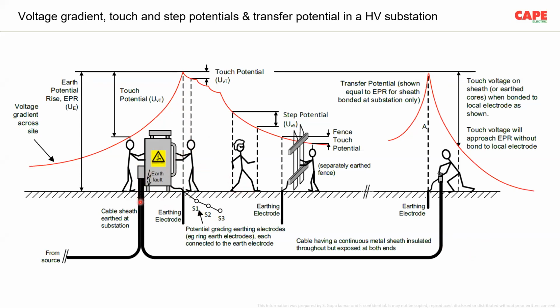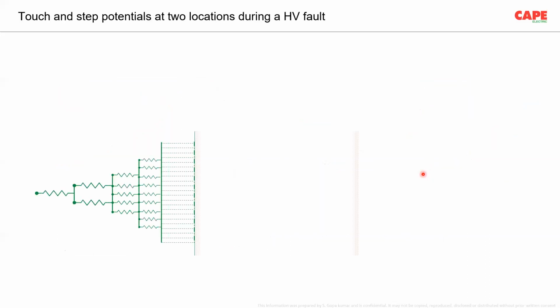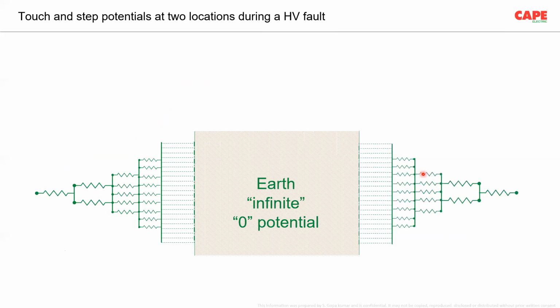Now the wire is also connected to a remote place. Let's say, for example, the armoring is connected to a different place. In that particular case, the armor also will carry the potential, and at a remote location, there can be a transfer potential. So for high voltage application, we are supposed to take care of step, touch, and the transfer potentials. Anyway, our subject is mostly low voltage.